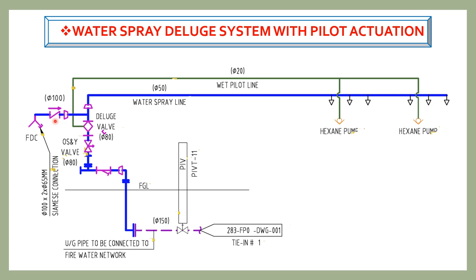Here is how the system works: when fire is detected near the hexane pumps, the pilot sprinklers activate, causing the pressure in the wet pilot line to drop. This pressure drop triggers the deluge valve to open, and water flows through the entire piping system, flooding the area with water from all the open nozzles to suppress the fire. The concept is the same for other actuation types — the only difference is the type of signal received by the deluge valve.